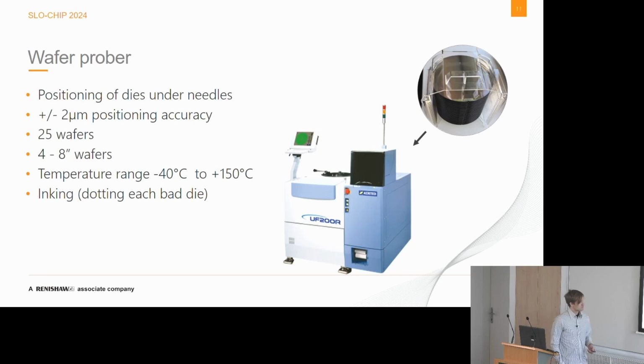Our prober has approximately plus or minus 2 micrometer positioning accuracy. We can load up to 25 wafers, a whole batch, in one go. 4 to 8 inch wafers are accepted. It also serves as a temperature regulator, so we can test our device across the whole temperature range, from -40 to plus 150 degrees. And if needed, you can also do the inking, as I've shown before.